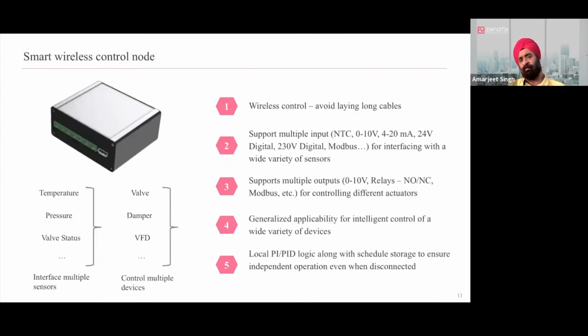As a second thing, what we built is a wireless DDC or a wireless PLC. You can think of it that way, right? So it's a card. Now this is not battery powered. It's a card which is a powered device, which has analog and digital inputs and outputs, and to which you can connect standard field devices, right? So you can bring in any standard 0 to 10 volt or 4 to 20 milliamp sensor, or 0 to 10 volt or 4 to 20 milliamp actuator, right? Or you can bring in any standard NTC, you can bring in any digital input, or you can bring in any actuator which has to be controlled on a digital output. All of those field devices can be connected to this wireless DDC or a wireless PLC.